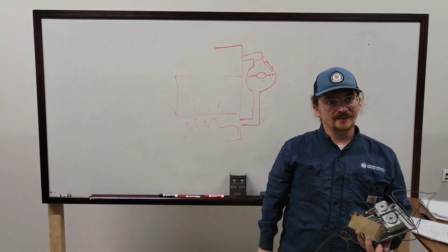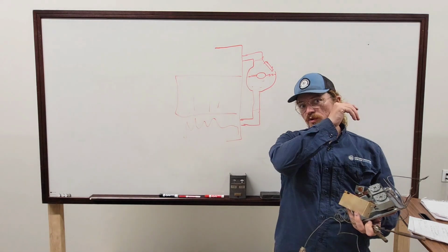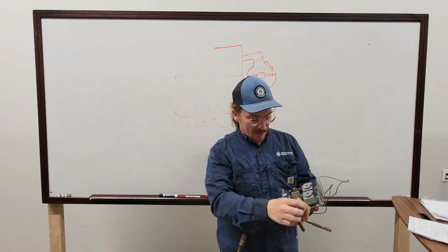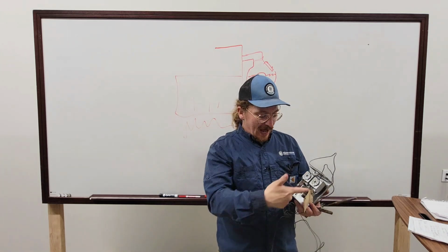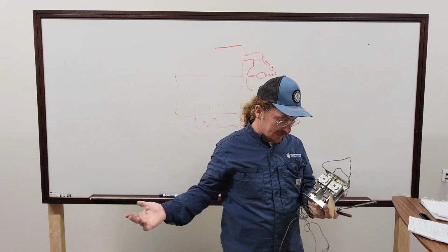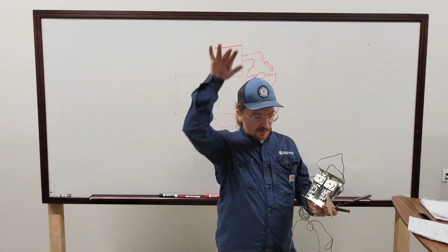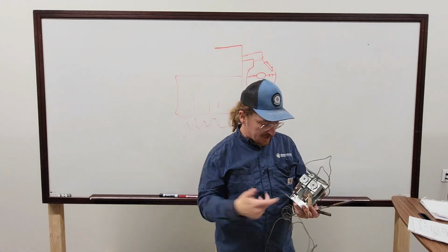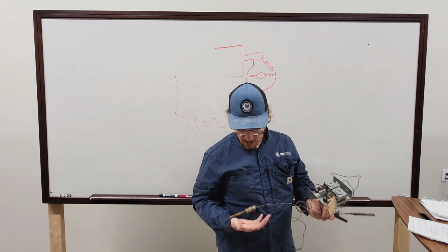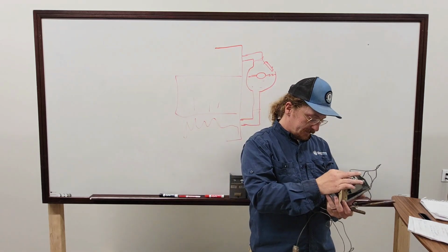Basically, your high-low, that is your essential thermostat control for the system, yeah? Yeah, in this case, this was set up as the control. So we have a high limit, so we're set to say 220. We're going to open the contacts. They're normally closed. They're going to open once we see a rise in temperature above our set point, which is, this one is 190. Because you don't want it above 200 because you don't want to make steam.